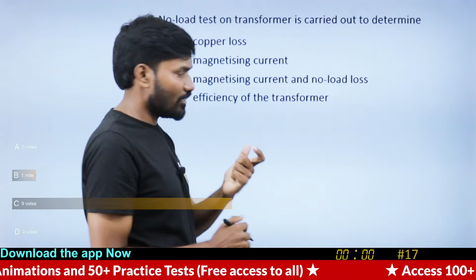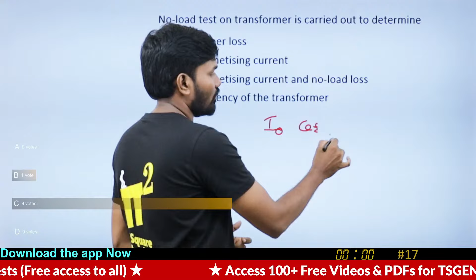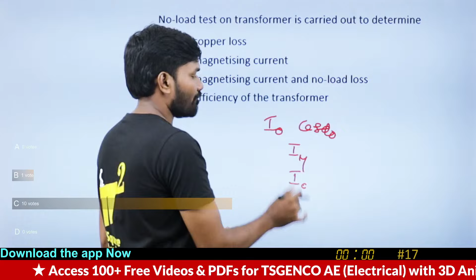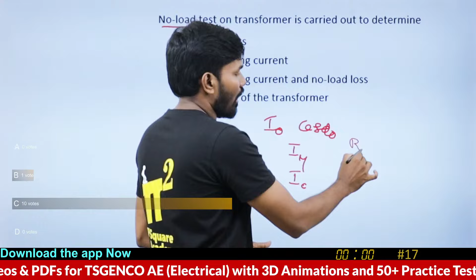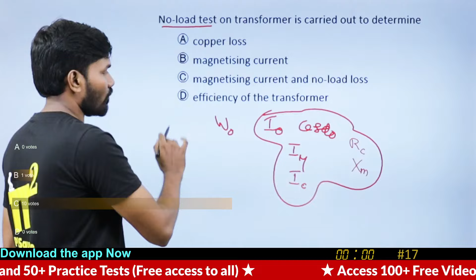So, the no-load test is for finding the magnetizing current. You'll definitely find I naught, and you'll find cos phi naught. From there you can find I mu, and IW or IC. You can find all these from the no-load test, and thereby find RM or RC, the core loss resistance, and also XM. So these are the parameters we're trying to find, and obviously the wattmeter reading, the no-load power, can also be found.